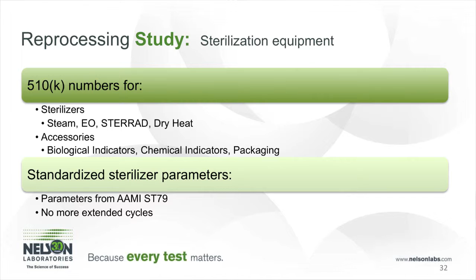FDA is also specifying that only standardized sterilizer parameters must be utilized for sterilization. We are not able to just set the sterilizer for any type of parameters. This just causes the healthcare facility a lot of trouble trying to perform specific sterilizer parameters for every type of set of medical devices out there.